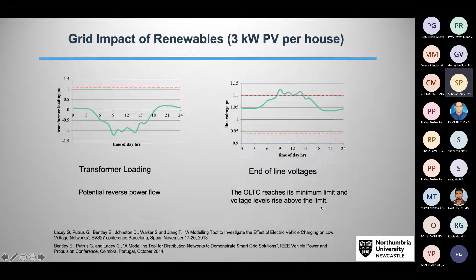We looked at different penetration of EVs charging, and we looked at 3 kilowatt charging. And here we looked at what we call dumb charging, people coming back from work at 5, 6 o'clock in the evening, everybody plugs in the car and starts charging. And we concluded that for every 10% increase in houses with EVs, the demand will increase by about 15%, if it is a 3 kilowatt charger. If it is a 7 kilowatt charger, the demand will increase by double, 30% for every 10% increase.